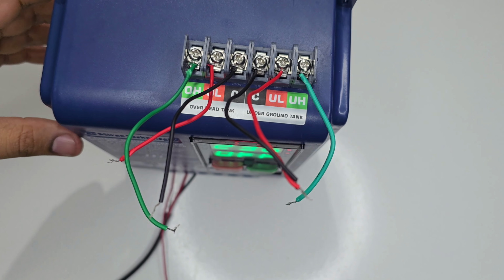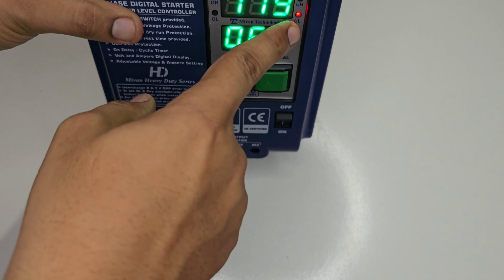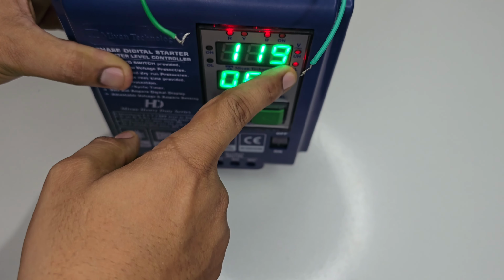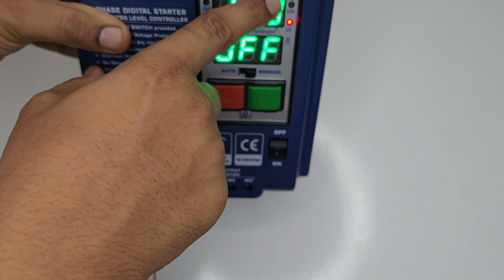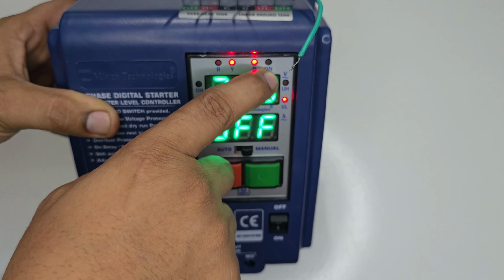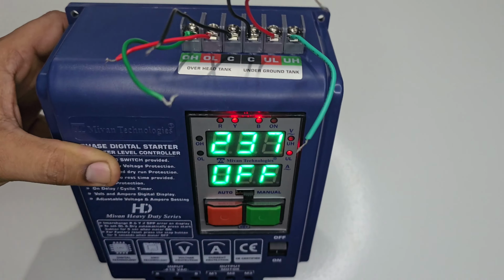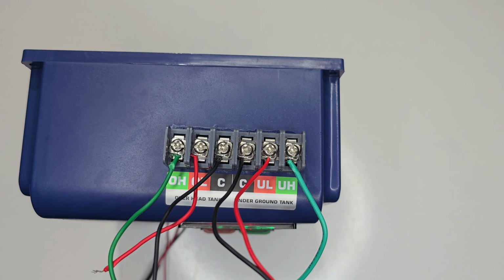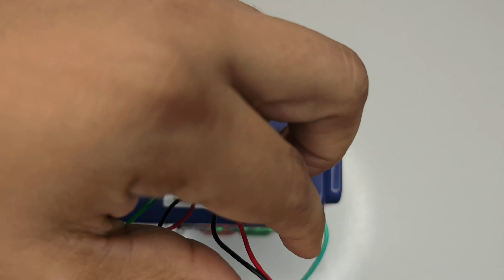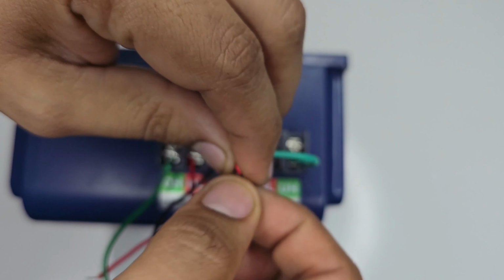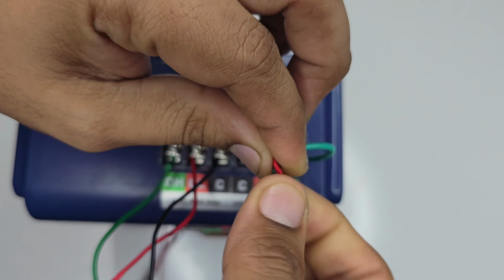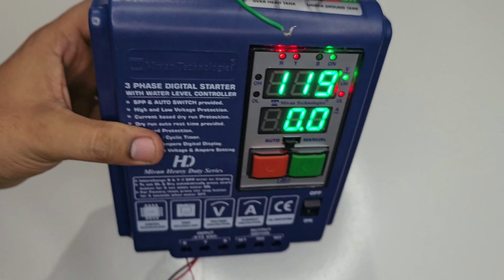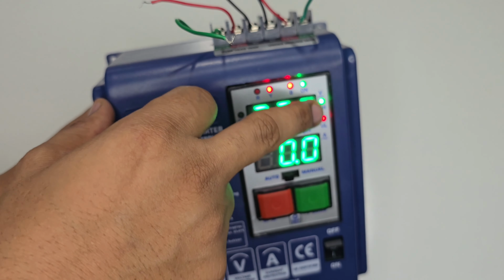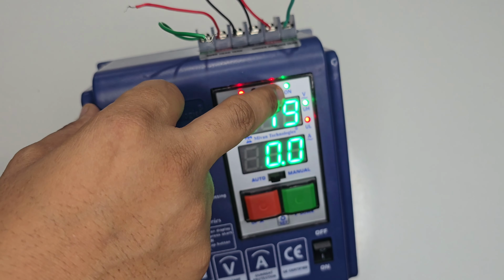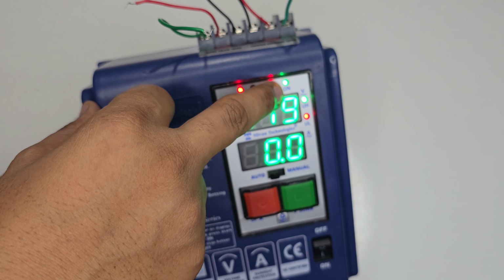When you short a C wire to UL wire, you can see the UL indication here and there is no ON indication. There is no ON indication and the UL indication comes. Now let's short C, UL to UH wire. You can get a UL and UH indications, and the ON indication also shows.